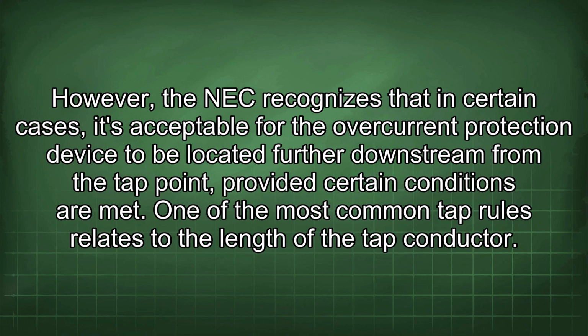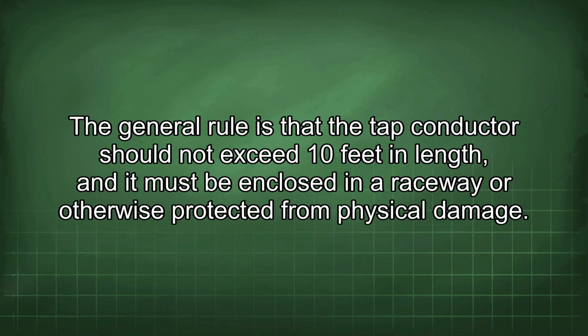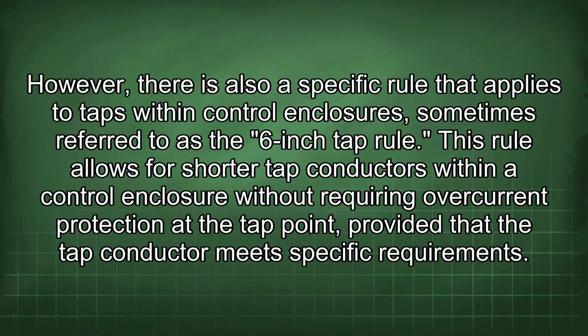One of the most common tap rules relates to the length of the tap conductor. The general rule is that the tap conductor should not exceed 10 feet in length, and it must be enclosed in a raceway or otherwise protected from physical damage. However, there is also a specific rule that applies to taps within control enclosures, sometimes referred to as the 6-inch tap rule. This rule allows for shorter tap conductors within a control enclosure without requiring overcurrent protection at the tap point, provided that the tap conductor meets specific requirements.